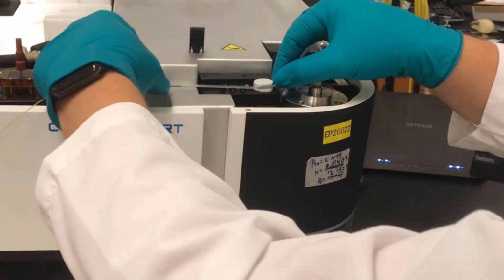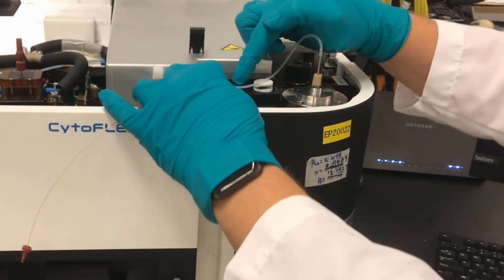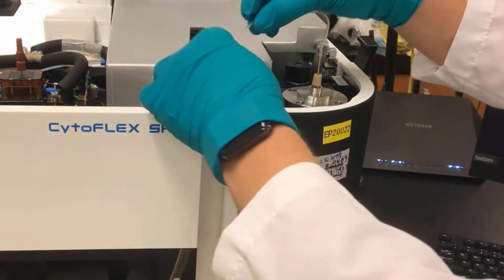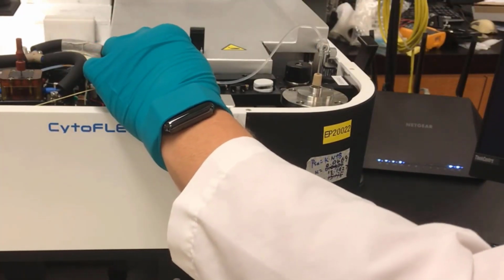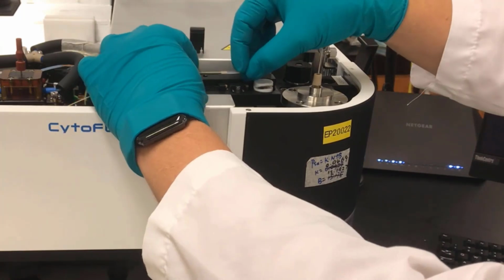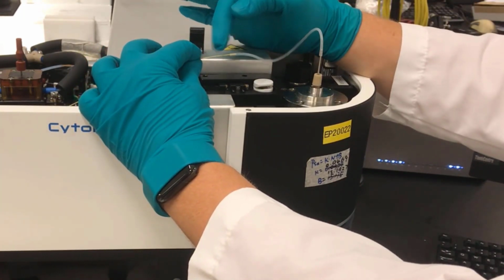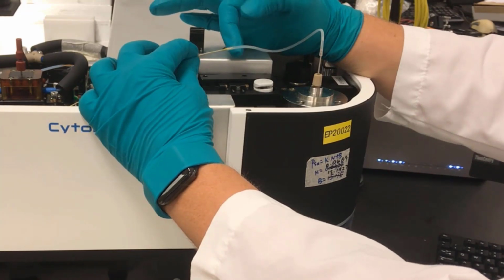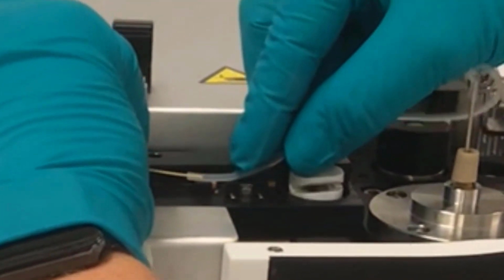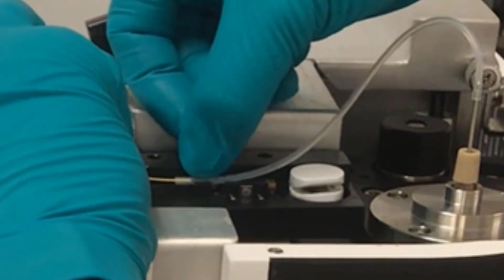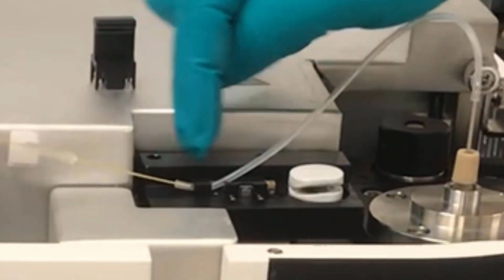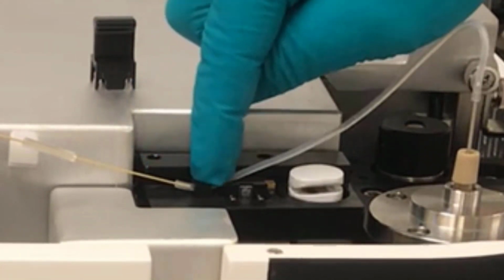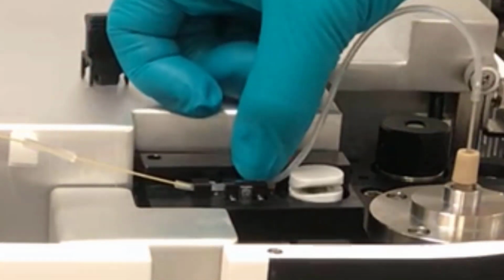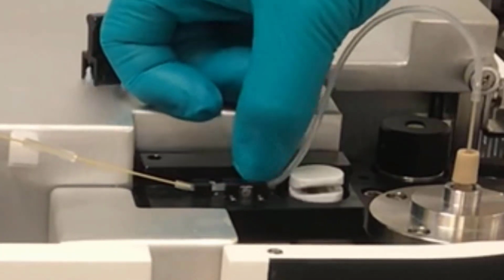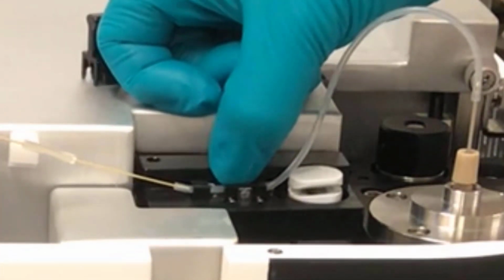Route the silicone tubing through the pinch valve and the bubble detector. To know the exact placement of the tubing, the PEEK tubing end should be in the middle as shown in the picture. Otherwise, the sample flow rate may be inaccurate, and the bubble detector function may not work properly. Push the silicone tubing into the sample line bubble detector slot. You can use your finger or a non-sharp object to help you push the sample line down. It doesn't require too much force.